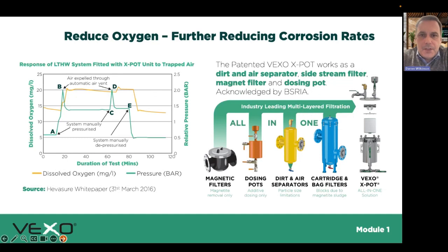So we need to try and reduce the oxygen, and that will help reduce the corrosion rate. There is a correlation between dissolved oxygen and what we'd call free air. And quite frankly, the difference is, if you imagine Henry's law, a fizzy 2 litre bottle of carbonated drink, within the bottle there's a standing pressure which is above atmospheric. That pushes a lot of any gases into solution. You can't see them until, of course, you unscrew the lid, and then you start to equalize to atmospheric. We reduce the pressure inside, and those dissolved gases come out.